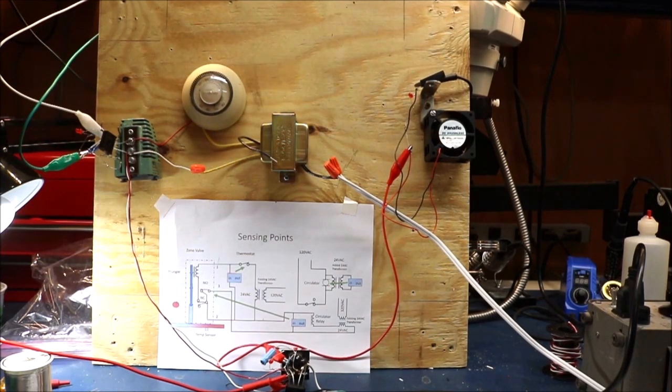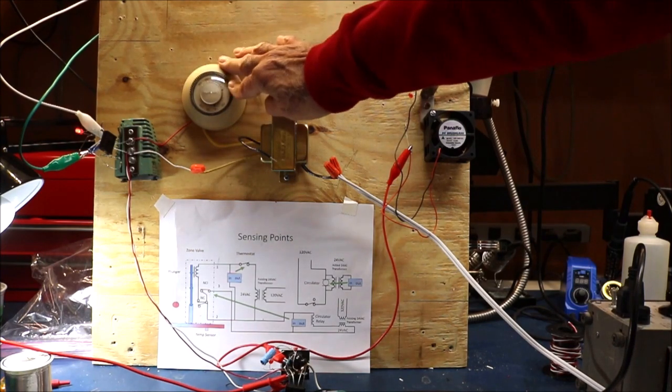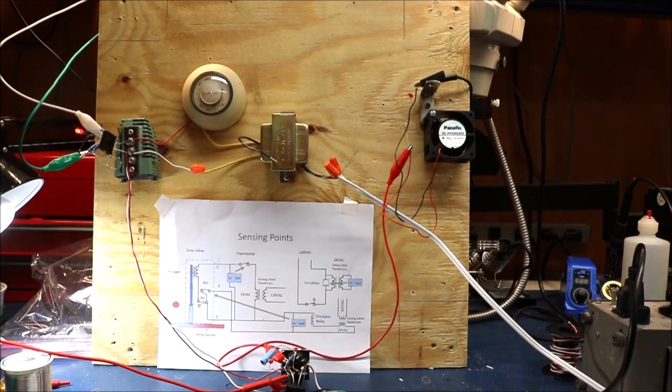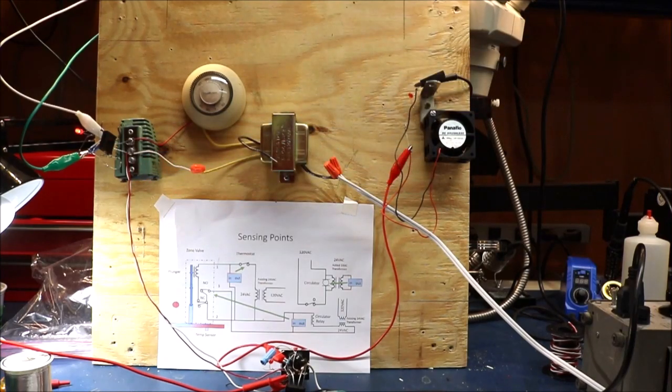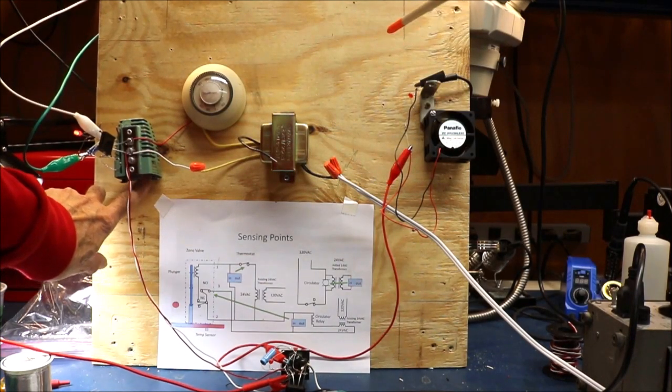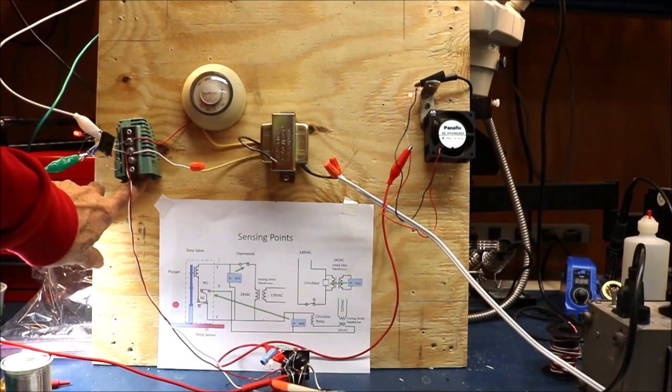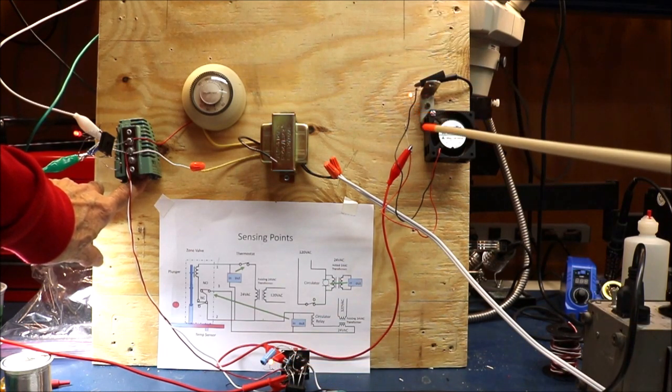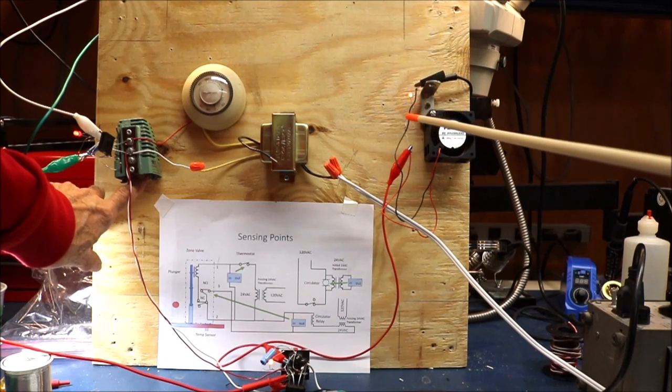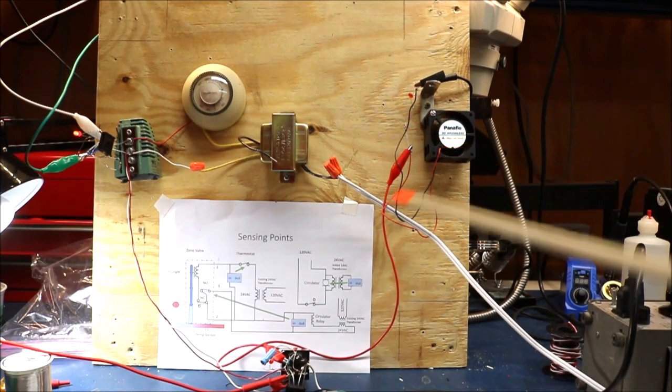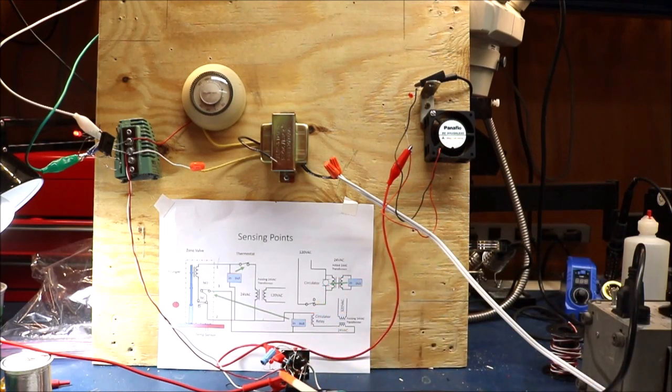First thing I'm going to do is turn on the thermostat. And you see the light here, which is what we said would happen. So now, if I manually close these contacts here, the circulator contacts in the zone valve, you can see the light on the circulator relay comes on down here. And the light on the circulator, or the fan, comes on as well. And when the contacts come off, both the circulator relay is not energized and therefore the circulator is not energized either.